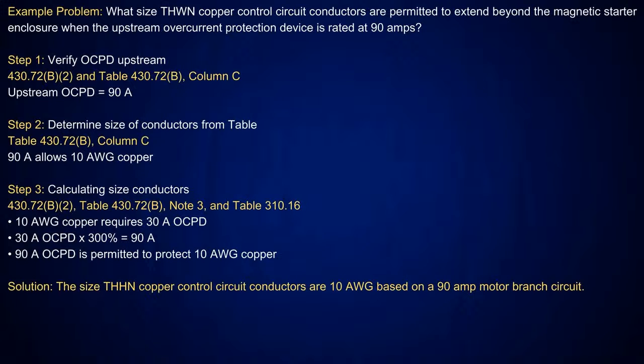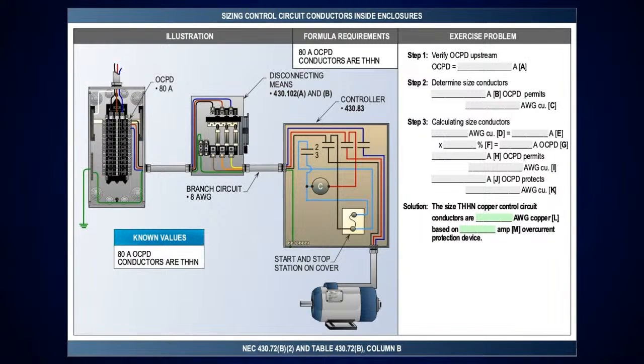Now, I do want to point one other thing out. The reason they're using table 310.17 is because you're in an enclosure here. And when you're within the enclosure, that's considered free airspace.